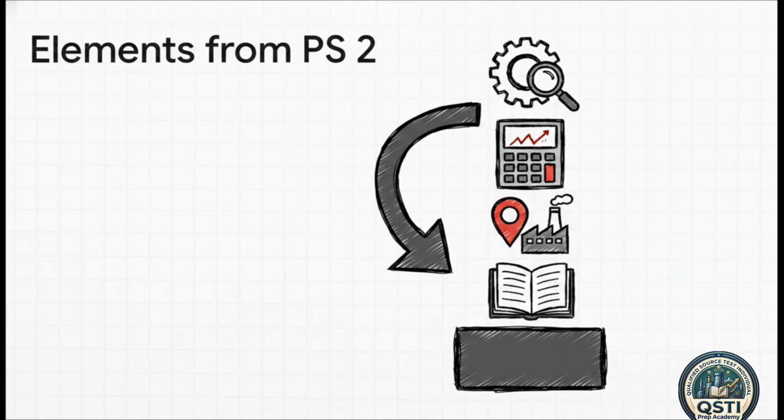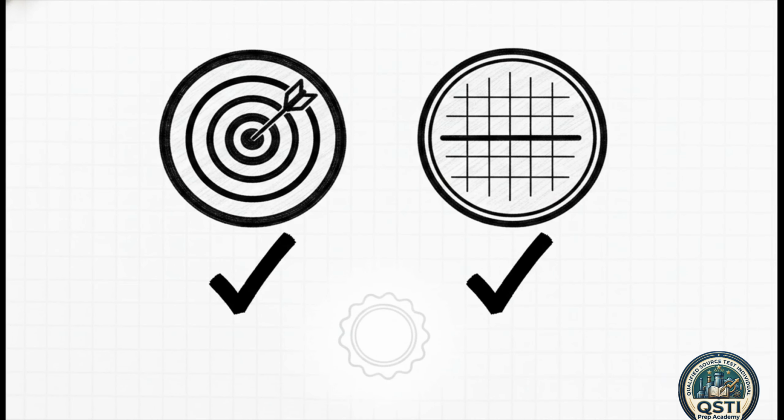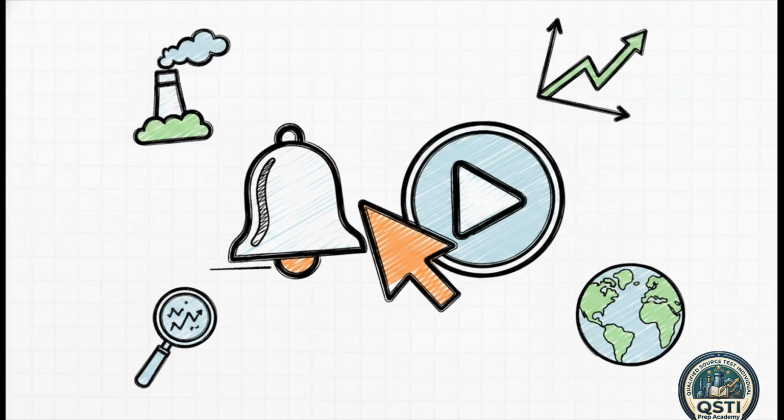They literally just lifted those rules straight from the SO2 and NOx playbooks and applied them directly to O2 and CO2. Because it borrows so heavily from that predecessor, the actual performance evaluation really just boils down to 2 core tests. First up is the relative accuracy test, or RA. And the second is the Calibration Drift test, or CD. Pass these 2, and your initial installation is golden. Now, we're about to dive deep into the math and methodology of exactly how those 2 tests are conducted.